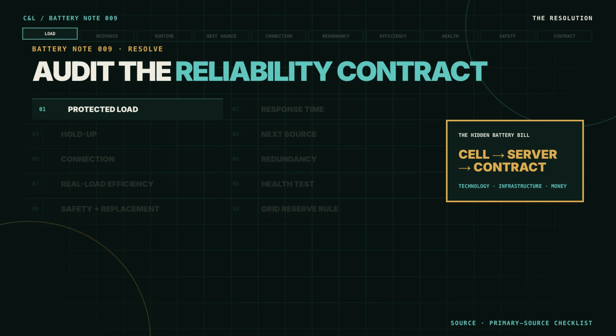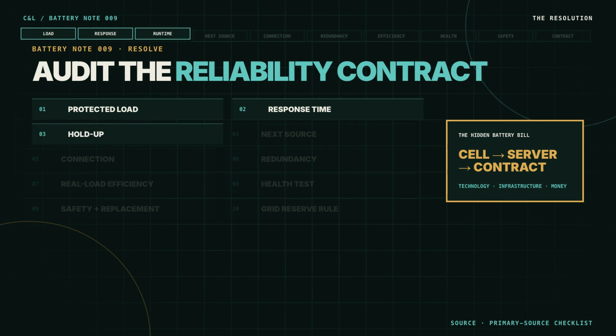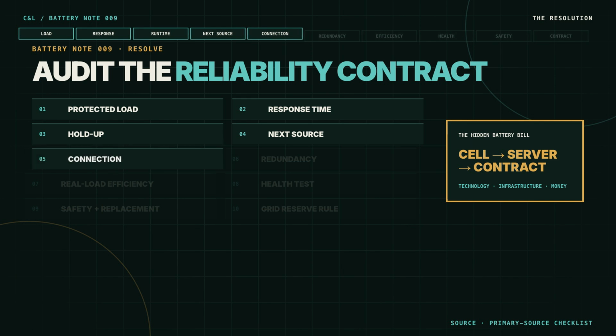What load is actually protected? How fast must storage respond? How long must it hold? What starts next? Where is the battery connected? What redundancy remains after one failure? What efficiency is expected at the real load? How are health, temperature, and state of charge tested? Who pays for replacement and fire safety compliance? And can grid service ever reduce emergency reserve? Those questions turn a generic battery quote into a reliability model.